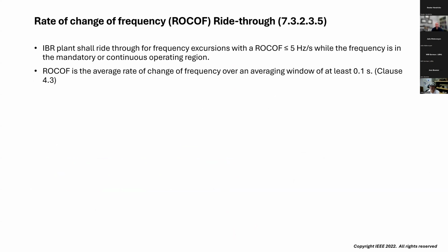So there are two final requirements that were lumped under the frequency section, one being the rate of change of frequency. The IBR plant needs to be able to ride through rate of change of frequency up to 5 hertz per second, assuming that the frequency is in the mandatory or continuous operating region. A key note here is how that's calculated. We need an averaging window of at least 0.1 seconds. So you can't take 2 samples very quickly, divide by a small amount of time and say that rate of change of frequency is greater than this, therefore I don't have to ride through. It needs to be averaged over this 0.1 second window.